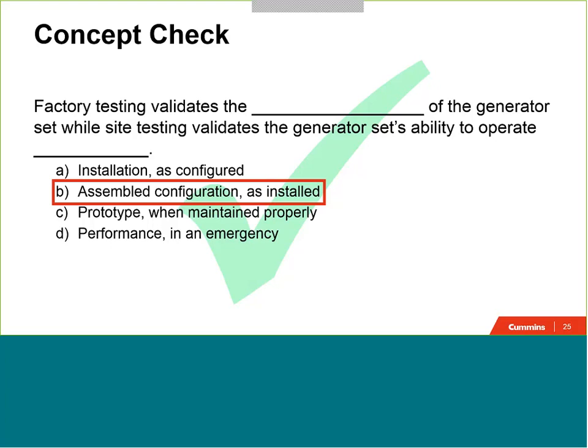Site testing is there to validate the generator set's ability to operate as it is installed on site. And I talked about the fact that site testing isn't testing just the generator set, it's also testing the way it has been integrated into the entire power system in the facility. And so in this case, we would definitely say that B is the correct answer.